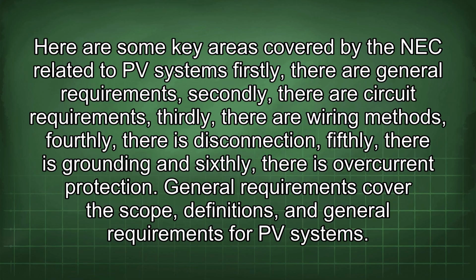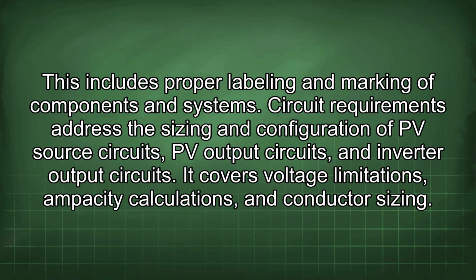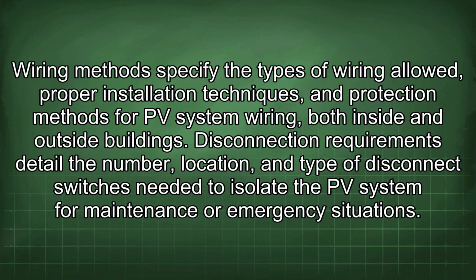General requirements cover the scope, definitions, and general requirements for PV systems. This includes proper labeling and marking of components and systems. Circuit requirements address the sizing and configuration of PV source circuits, PV output circuits, and inverter output circuits. It covers voltage limitations, ampacity calculations, and conductor sizing. Wiring methods specify the types of wiring allowed, proper installation techniques, and protection methods for PV system wiring, both inside and outside buildings. Disconnection requirements detail the number, location, and type of disconnect switches needed to isolate the PV system for maintenance or emergency situations.